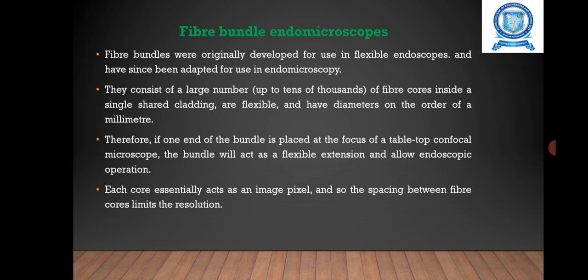Here each core essentially acts as an image pixel, and so the spacing between fiber cores limits the resolution. The addition of micro optics at the distal tip of the bundle allows for magnification and hence higher resolution imaging, at the cost of reducing the field of view.